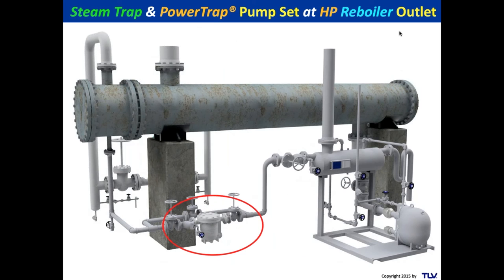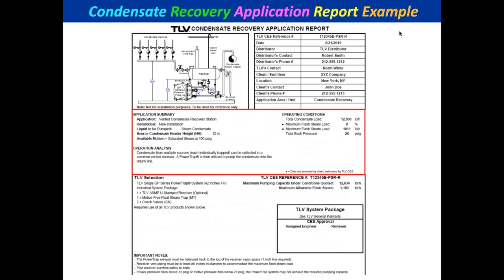A simple solution might be to put a trap into a pump set. You'll need to deal with the vent, but it gets condensate out without discharging to grade and allows recovery. For a trap going into a pump set, we use a Condensate Recovery Application — CRA. Like all our forms, CRAs are checked by four people. The data section gives you the load, the flash load, and the required flash piping size.